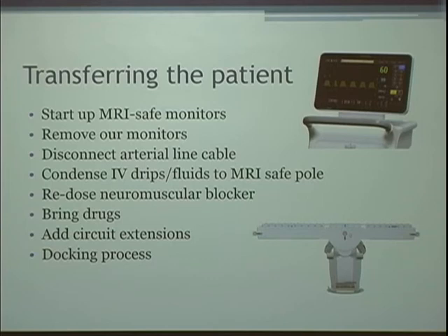At this point, you can transfer your sample line with your capnograph over to this monitor as well, and then disconnect your A-line cable. You can bring the A-line transducer that is considered MRI conditional. It is safe for our scanners. You can bring the transducer and the pressure bag into the room, but you won't be able to actually transduce your line because our cables are not MRI safe. But you can at least keep your A-line from clotting off. Try and get everything condensed onto just the MRI safe pole so that you're only wheeling one pole in with the patient.